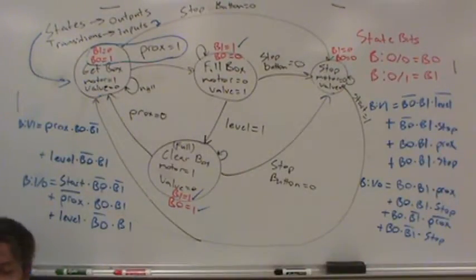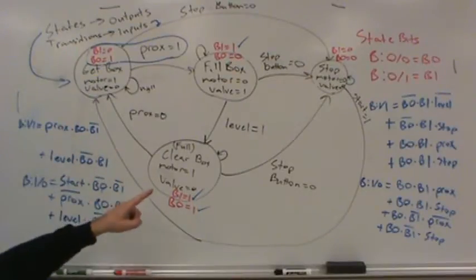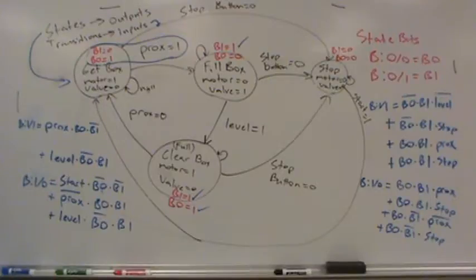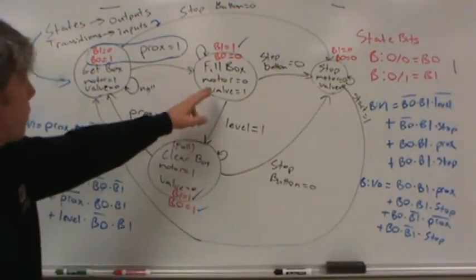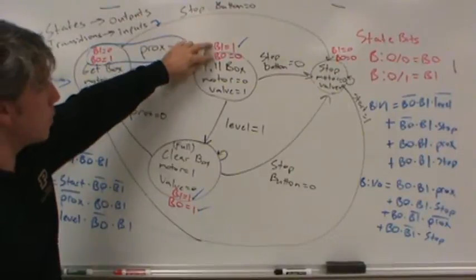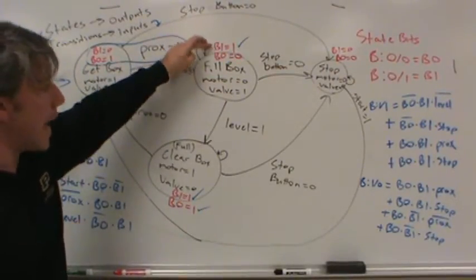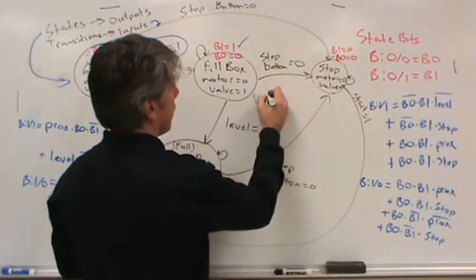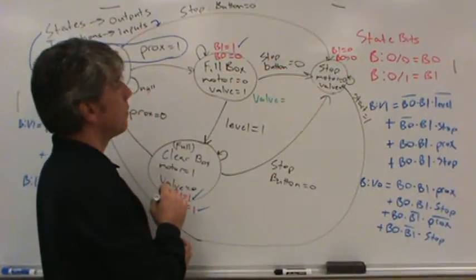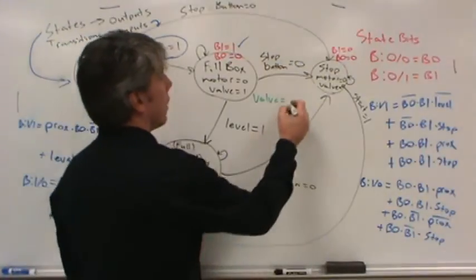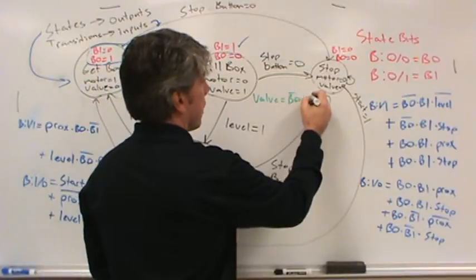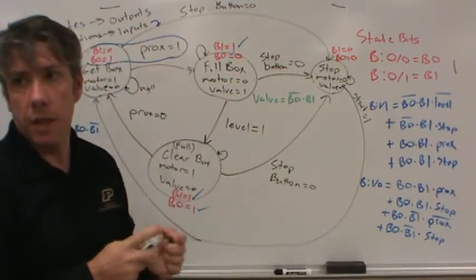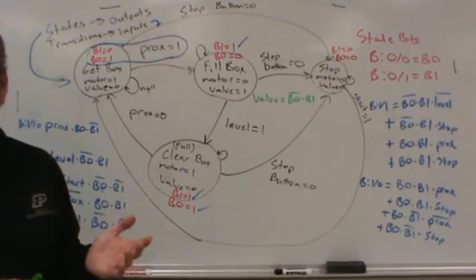Now, if I download this and run it, you know what's going to happen? Absolutely nothing. Why? Because we haven't programmed the outputs yet for the states. We've got to make the mechanical system actually do something. But that's actually really easy. All you do is you program ones again. We don't have to worry about these two. But wherever valve is one, we just say, okay, what are the state bits? Those are the conditions for valve being on. Any time B0 is a zero and B1 is a one, valve is equal to one. So help me write down that equation. So valve is equal to what? B1 and not B0. Not B0 and B1. If we put them in the same order we've been putting them. I've done this all. Right? See how easy that is? It's simple. That's the output for the valve.